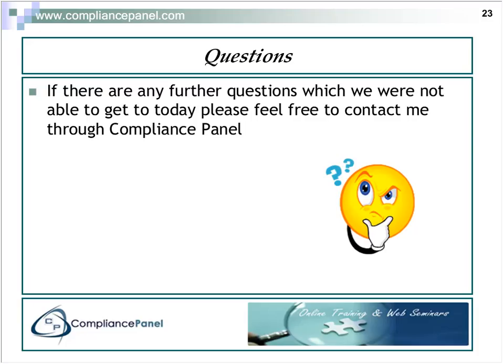So if there's one thing I can convey to you, if you're not already doing that, which I know most companies are already doing, it's that you seriously sit down and try to put down on paper what do I actually need in my DMR and what do I actually need in my DHR to show that I'm meeting that. So that would be my concluding statement here.